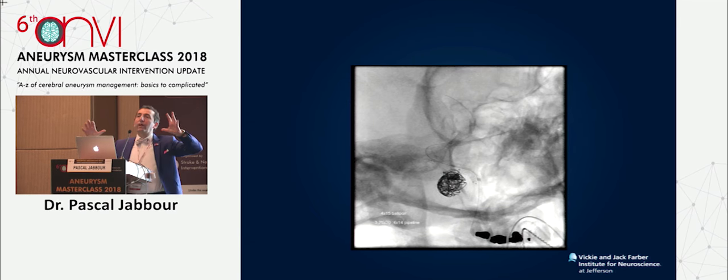Well, theoretically, flow diversion is made to be placed opposed to an endothelium. Here you're not opposing it to an endothelium, you're opposing it to a foreign body. So you're not going to be as tight and as covering as you want. It'll be just like a double stent, like the Fred. The issue with the Fred device is they took two stents and put them together. It'll be similar to that. There are issues sometimes with that, and sometimes trapping of air.